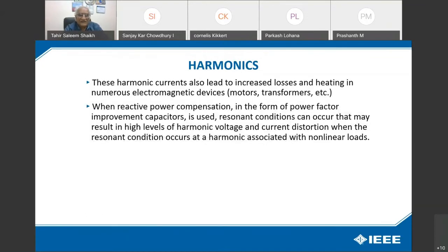These harmonic currents also lead to increased losses and heating in numerous electromagnetic devices, motors, and transformers. When reactive power compensation in the form of a power factor improvement capacitor is used, a resonant condition can occur that may result in a high level of harmonic voltage and current distortion when the resonant condition occurs at a harmonic associated with non-linear loads.